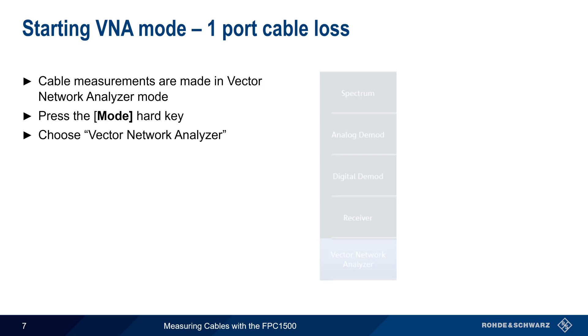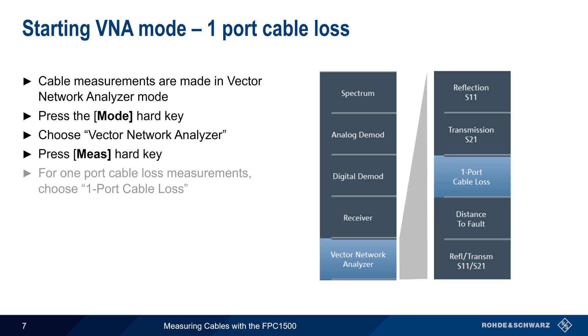Cable measurements on the FPC-1500 are made in Vector Network Analyzer mode. To enter this mode, press the Mode hard key on the front of the FPC, and then choose Vector Network Analyzer. Next, press the Measure hard key and choose One-Port Cable Loss.